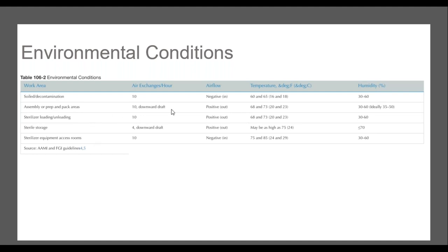Assembly or prep and pack areas: positive pressure, 68 to 73°F. Same for sterilizer loading and unloading. Sterile storage: positive pressure, temperature may be as high as 75°F, and less than 70% humidity.